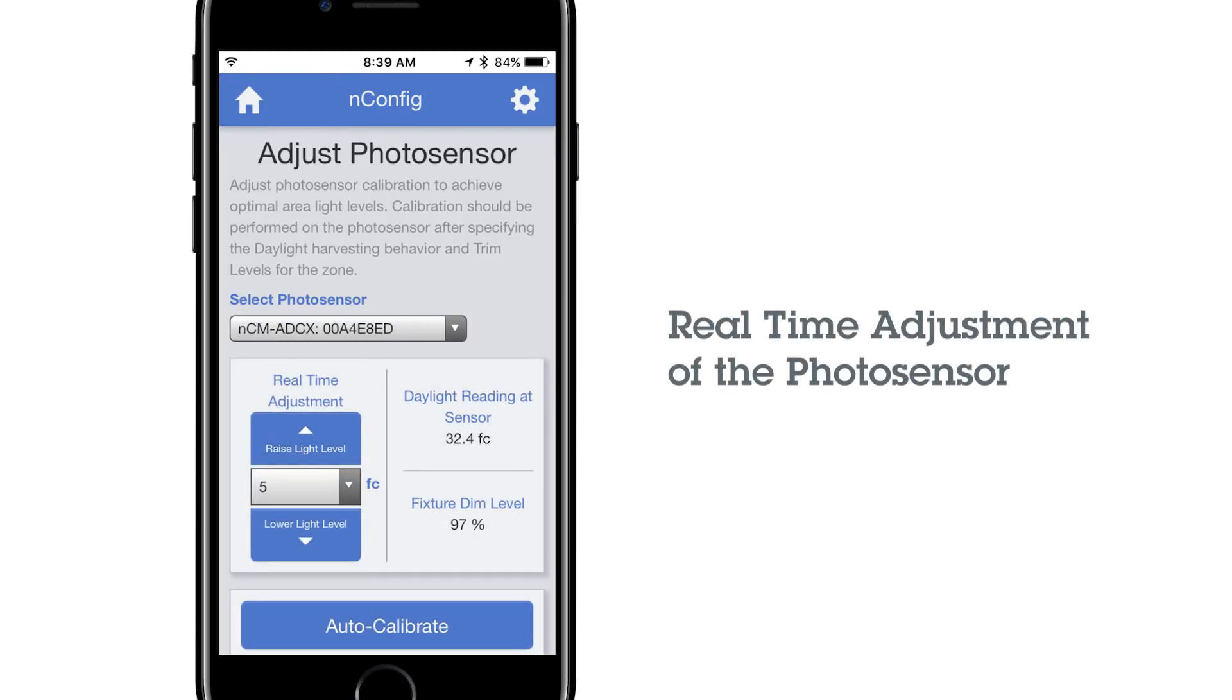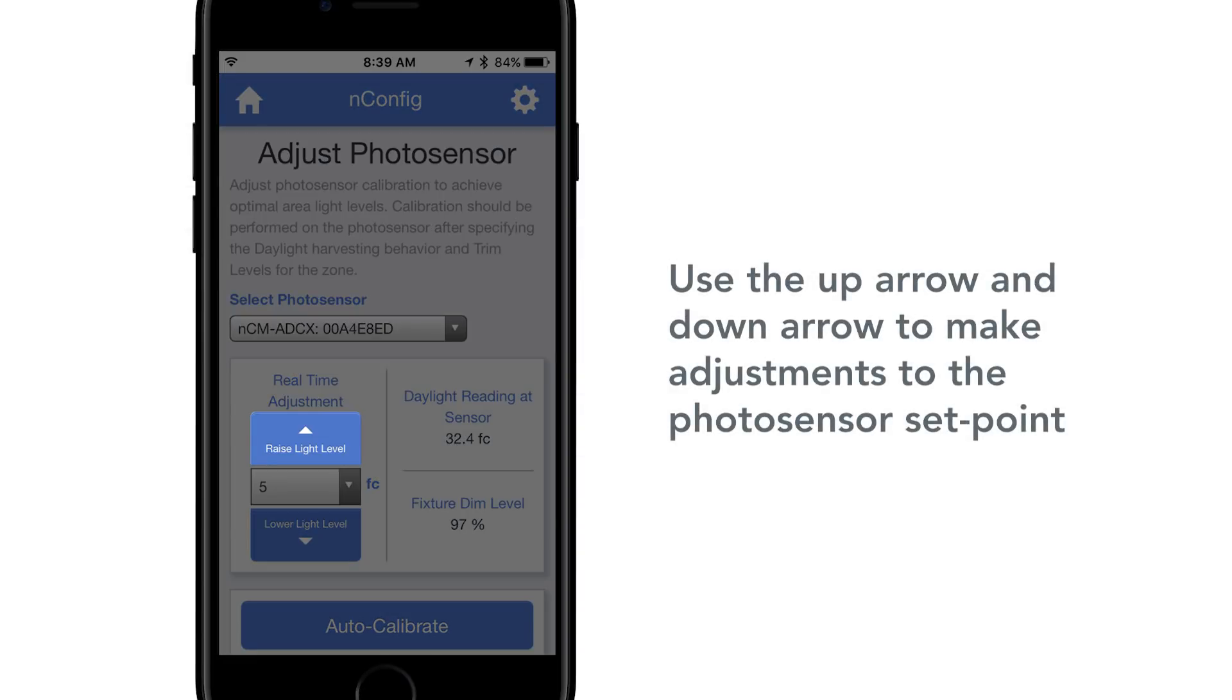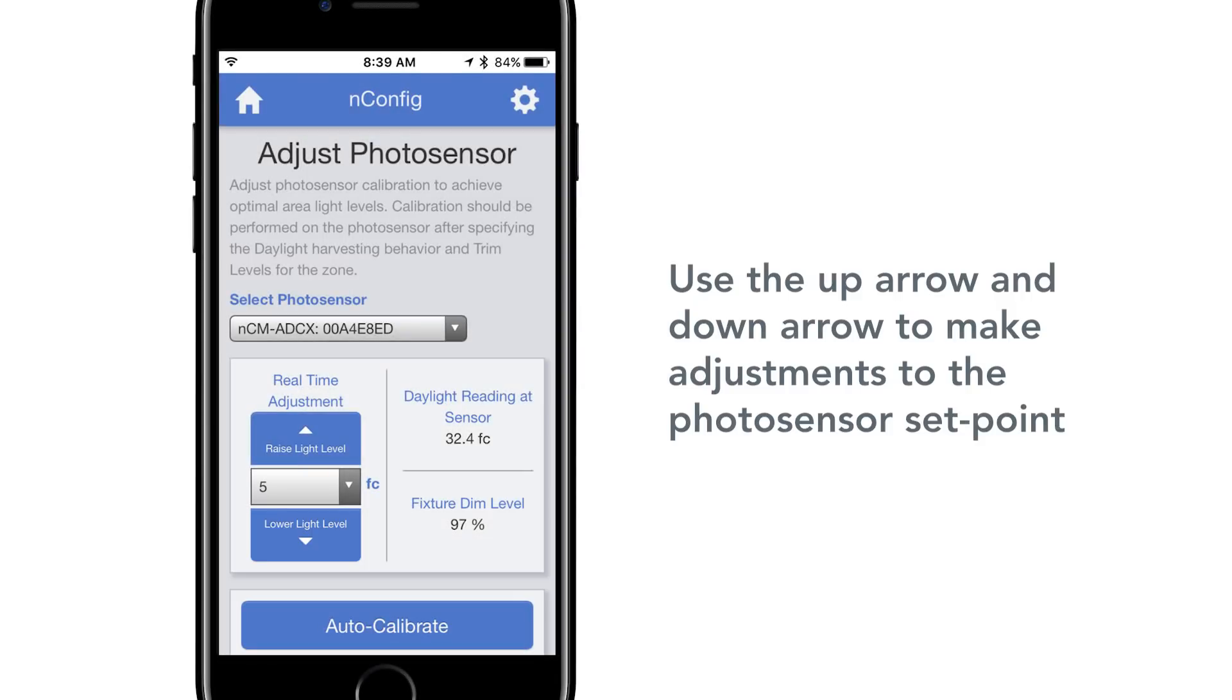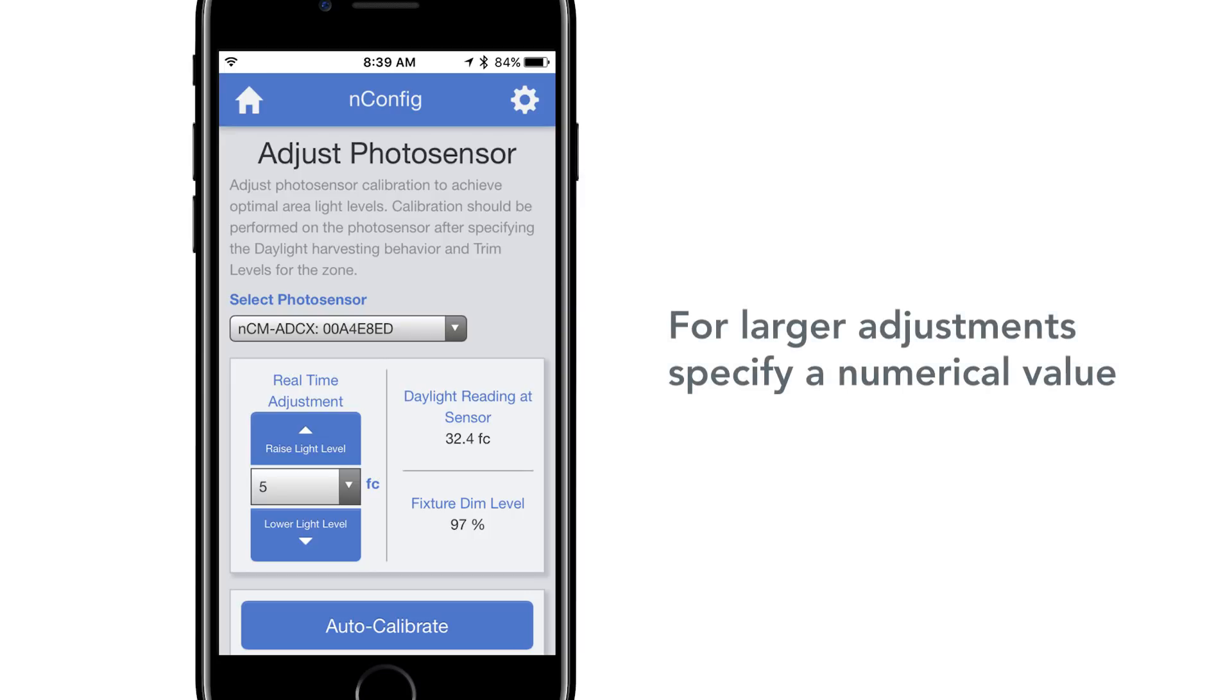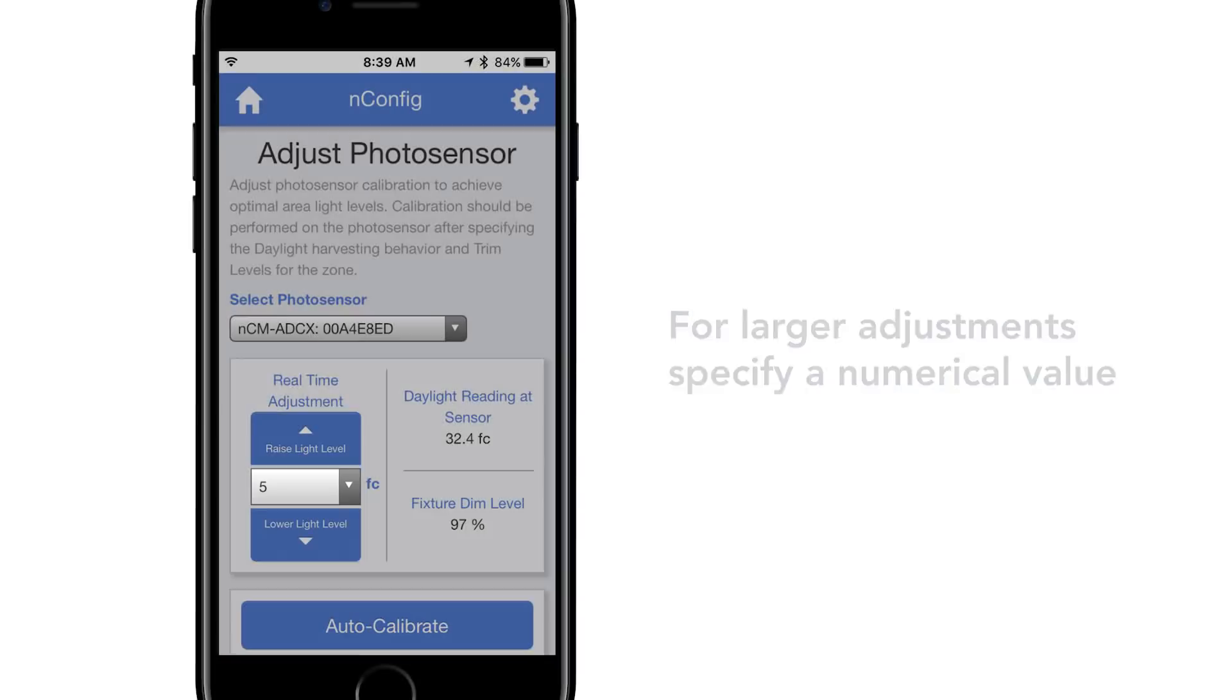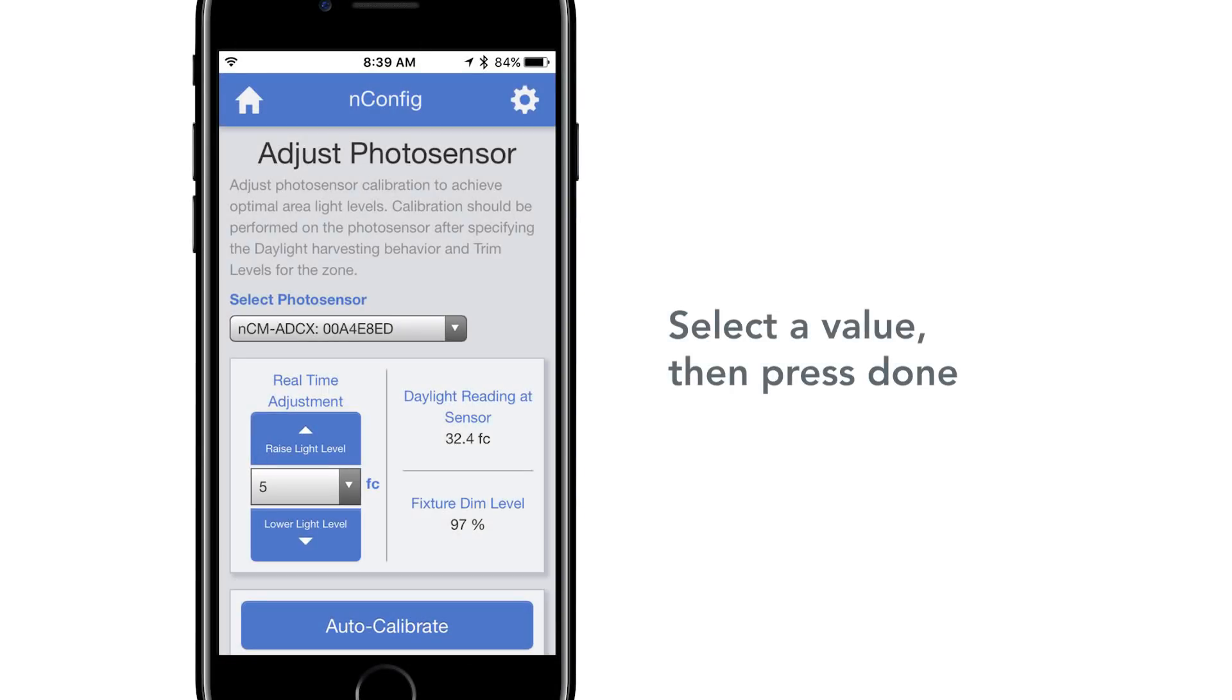If you are only looking to make minor adjustments to the Photosensor, the next step is the following. Use the up arrow and down arrow to make the desired adjustments to the Photosensor's set point, which is the light level that Photosensor is attempting to maintain. If you want to make larger adjustments, specify a numerical value between the arrows by selecting a specific foot candle level. Tap the numerical value to expand the drop-down. Select a value then press Done.